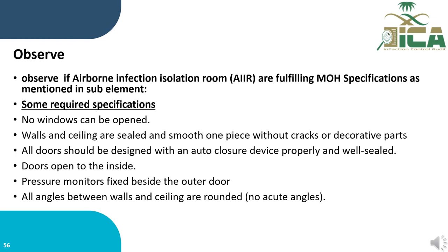This includes: no window can be opened; walls and ceiling are sealed and smooth, one piece without cracks or decorative parts; all the doors should be designed with an auto closer device, and the door opens to the inside; a pressure monitor is fixed beside the outer door; and all angles between walls and ceiling are rounded with no acute angles.